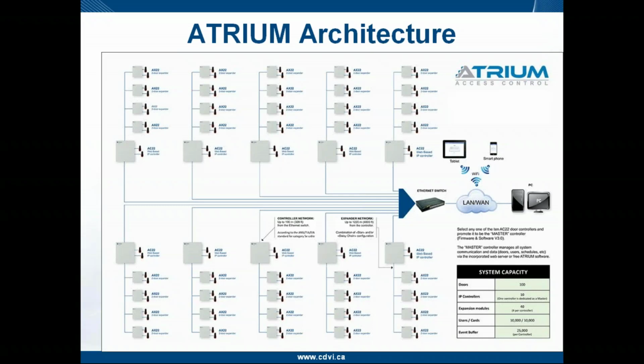So the offline mode is good for 7 days, 24 hours a day. You can restrict that or modify that down to a couple hours if you wish, 1 or 2 hours, or you can increase it all the way up to 1 year. So when the expander goes offline, how long will it continue reading the cards that were in its card buffer at each reader? Okay, so an important aspect.